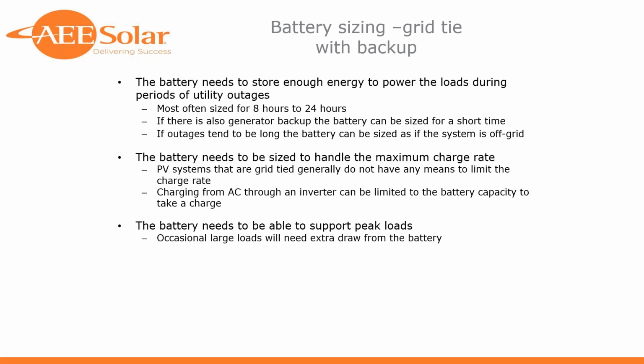Sometimes, if you're looking at just a short backup time, the battery is going to be somewhat smaller than what you would have for an off-grid system. And you do need to be aware of the battery being able to absorb the solar charge that it's going to be exposed to. Not all batteries can take whatever charge you push on them. Sometimes it will damage them if you push them too hard with too much charging, and may overheat them and damage them.